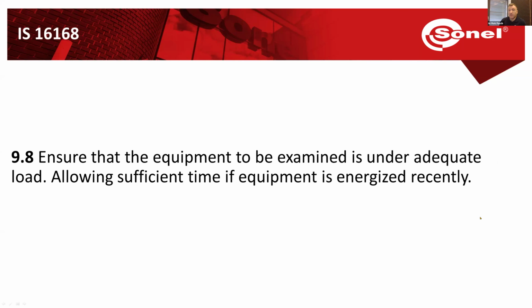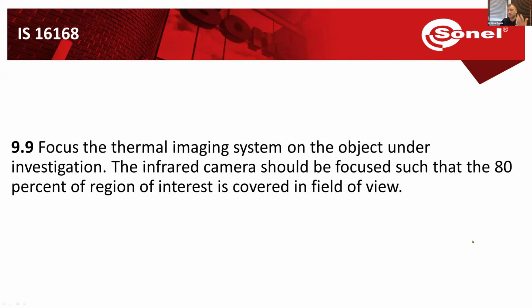We need to ensure that the equipment we want to examine is under adequate load. If there is no load, there will be no current flow, and nothing will heat or overheat in our electrical installations. That's why we want to make sure our installation is live, energized, and the loads are connected.